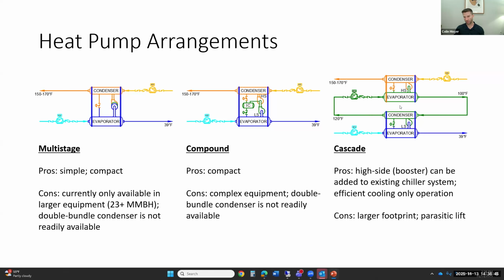You've got a differential temperature on that intermediate loop, and you've got another approach on the tubes of the other evaporator. So you're doing a lot more overall lift than you actually needed to do to get from 39 to 170. But the upside of this is that you have a lot of flexibility because you do have now an intermediate fluid loop, and you have regular chillers here, and you can mix and match operations.